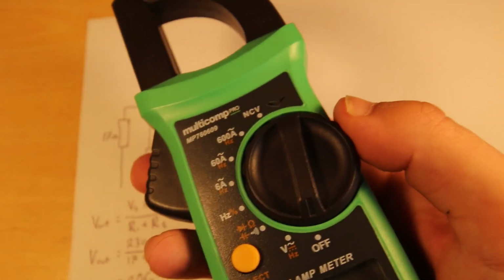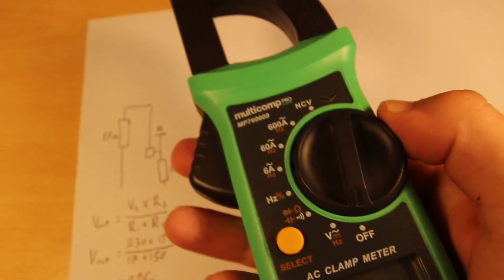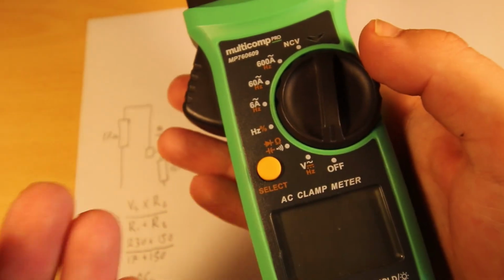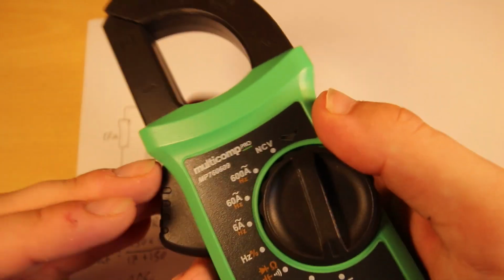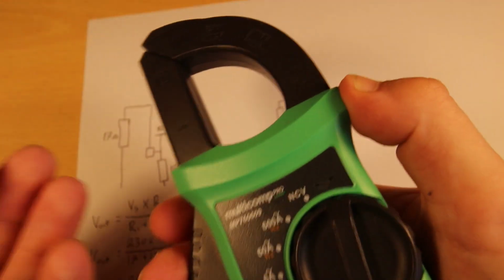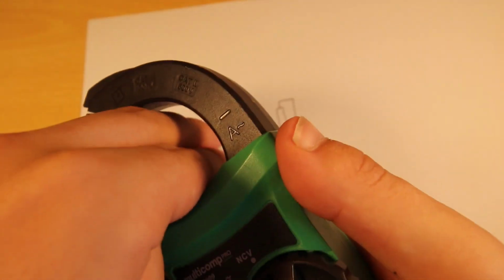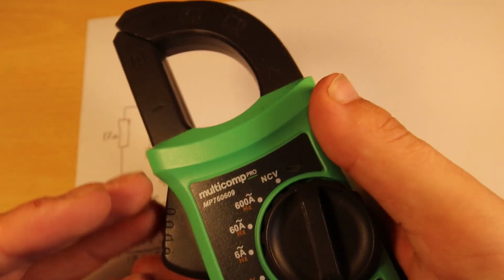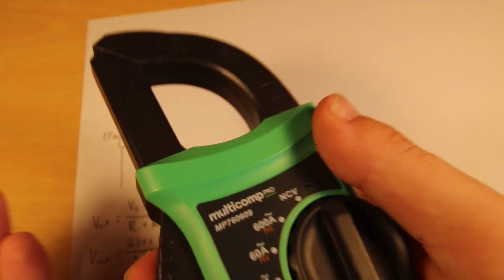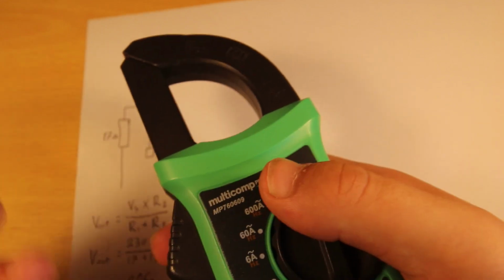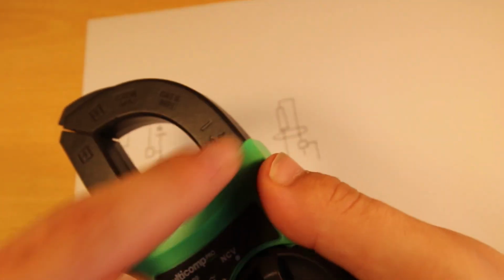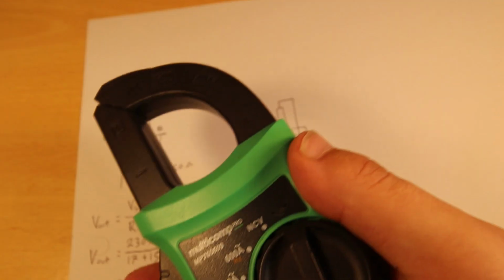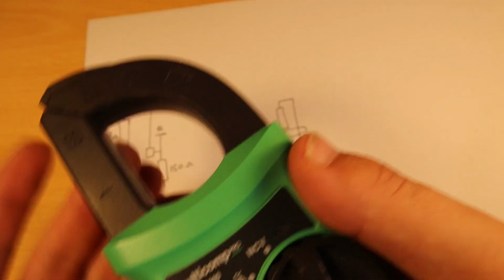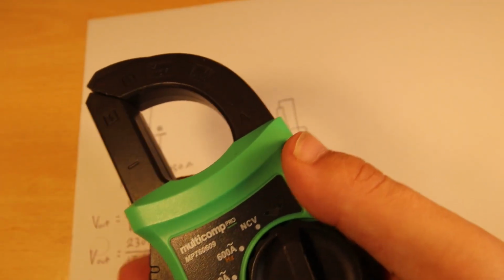You can also use it to measure leakage. This one is not a leakage clamp. I would say you should get a leakage clamp if you want to measure leakage. But the way you do that is you put all of the conductors you want to tell what is leaking from through here, and it will tell you what the current that is flowing up and not back is, which is the same way an RCD works. Actually, it has a current sensing coil like this, and it tells the difference between the current flowing up the live and back the neutral.